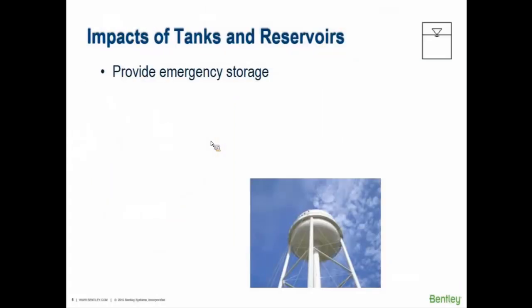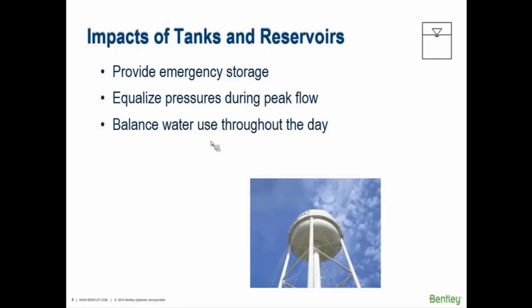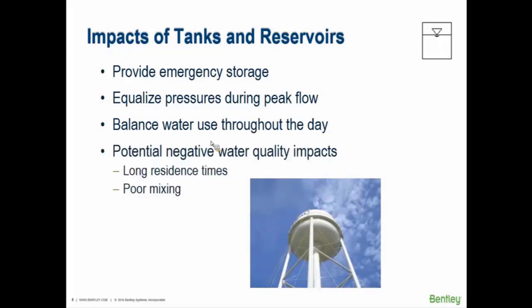Tanks provide emergency storage and help equalize pressures during peak day and maximum day demand, balancing the water out. We'll look at tank operations and how they fluctuate in more detail as the course progresses. However, tanks can potentially cause water quality issues — a wide tank may not mix well, an oversized tank may have long residence times, chlorine may drop, or tank water temperatures may rise.